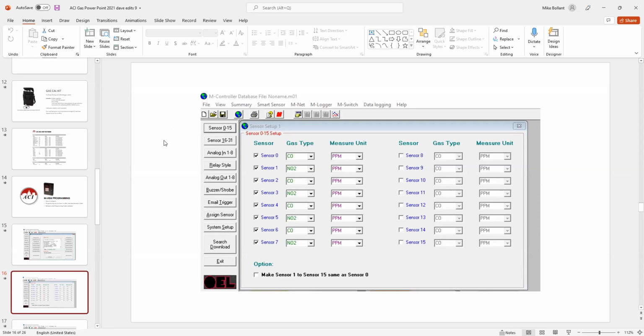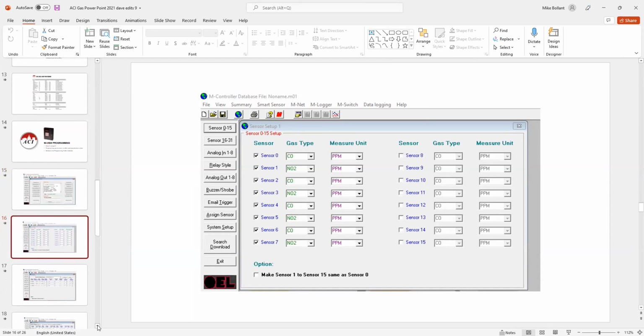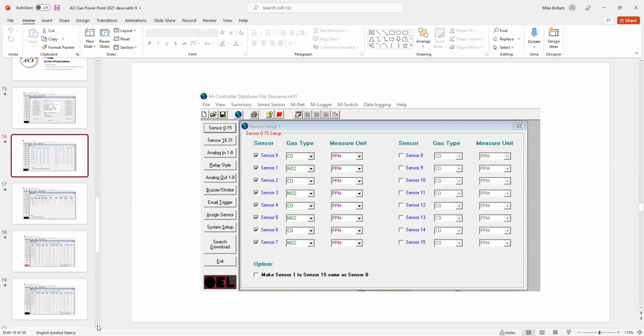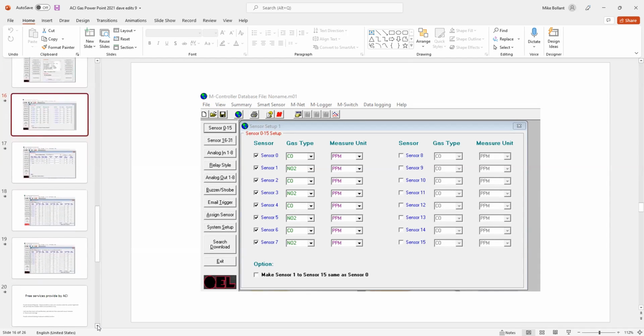Right here, so you can determine what the sensors are going to be. In this case, we're using, let's just say, the Q6 with CO and NO2. There's going to be 4 locations. When you enter the CO in here, or the Q6s, the main is always, remember, going to be even. When you start at 0, the odds are going to be 1. So we enter the gas type, CO and NO2 parts per million.